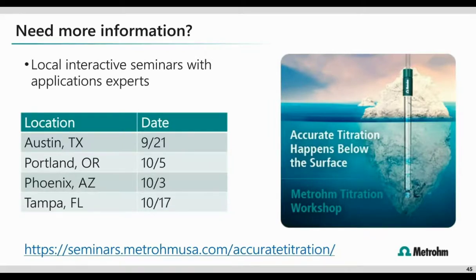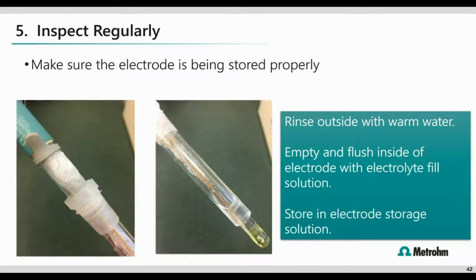Excellent, thank you. Now our next question says, how often or how do you know when to empty the electrolyte and not just top it off? Sure. When you're in everyday use, you should give it a peek every day and have a squirt bottle beside there and top it off daily. If it has been left open for an extended period of time, so if the fill port was left open overnight or over a long weekend, you may need to look a little closer and make sure that we haven't developed salt crystals around that top portion or on the inside of the electrode. Once those develop on the inside, we definitely need to get those removed and completely empty and refresh it.